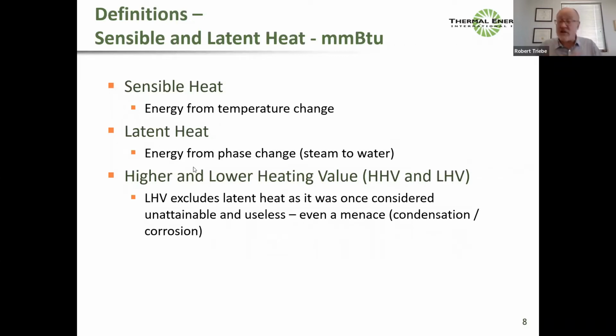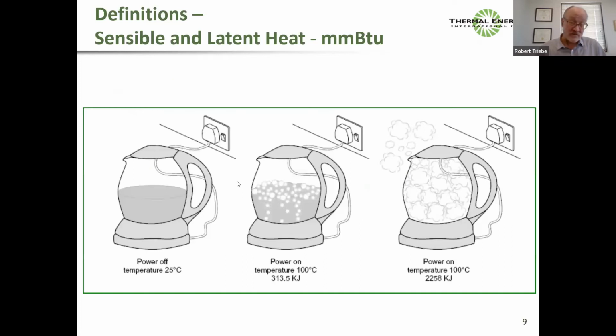And when we go to China, we often still see people saying they're 98% efficient. And when we tell them that we can do heat recovery based on a lower heating value, we actually tell them that we're going to bring them to 112% efficiency. And that's very hard to convince people, but based on lower heating value, that's the case. But the truth is, of course, latent heat is quite useful, and that's the whole purpose behind the condensing technologies.